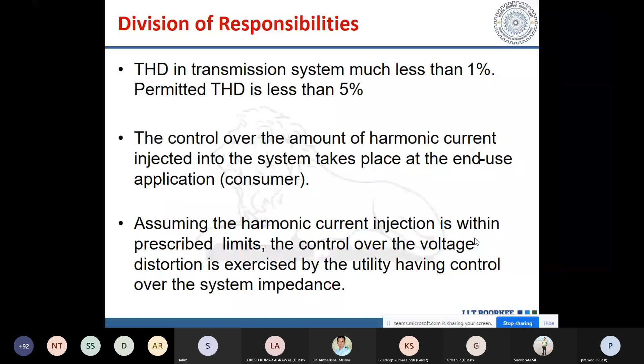Even if the harmonic current is within the permissible limit, 5%, the voltage distortion may be more than the permissible limit because of the impedance of the transmission line and the transformers used in between. So it is possible that the user has used very high power factor type converters, what we discussed in that particular class, and therefore the harmonic currents injected are very, very small. But even with these small harmonic currents, due to poor quality of the supply, due to high impedance of the transmission line and the transformer used in between, the voltage at the user end is not sinusoidal and the THD is more. So what is done?